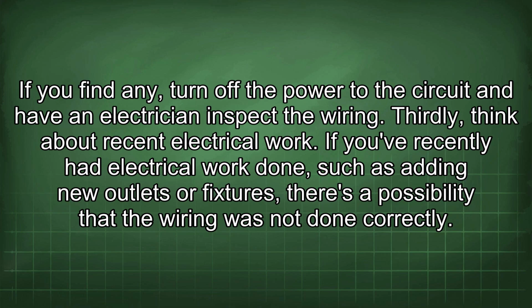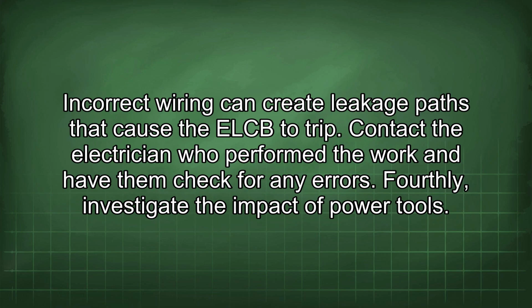Thirdly, think about recent electrical work. If you've recently had electrical work done, such as adding new outlets or fixtures, there's a possibility that the wiring was not done correctly. Incorrect wiring can create leakage paths that cause the ELCB to trip. Contact the electrician who performed the work and have them check for any errors.